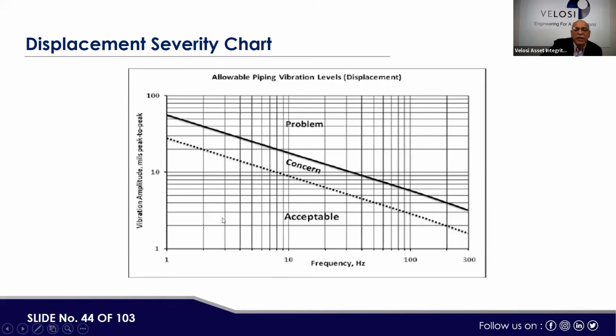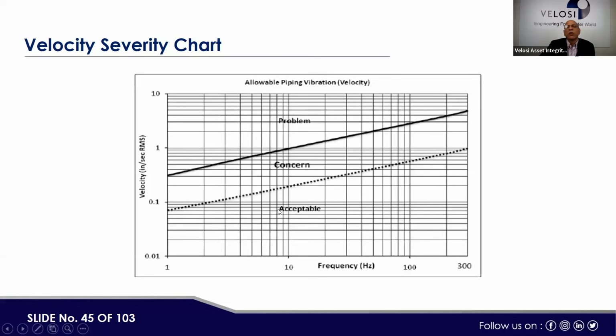And when we measure the vibration, we need to make sure all piping systems in the plant remain within acceptable range. Another one, like a velocity point of view, this is inch per second RMS, and it's also linked with the frequency or hertz, at what frequency the piping system is moving. And here, this range is acceptable, and then concern, and then the problematic area. So it's quite simple guidelines that are provided by Energy Institute and other standards, and if we follow them, we can have a proper control on the system.